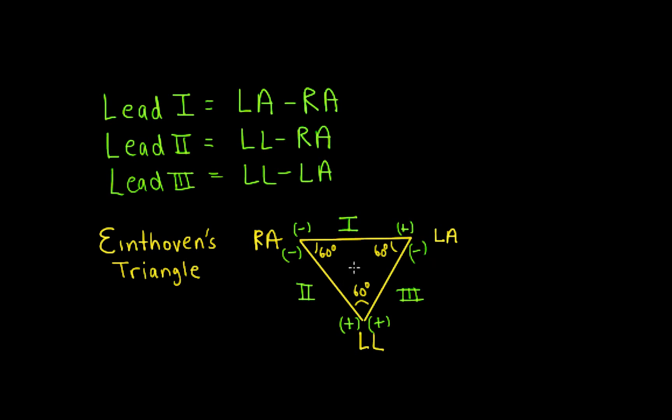If you look at the way the leads are organized, you can see that lead 1 plus lead 3 equals lead 2. The left arm electrodes cancel out when you add lead 1 and lead 3, and you're left with left leg minus right arm, which is lead 2. This relationship — lead 1 plus lead 3 equals lead 2 — is known as Einthoven's equation. It's good practice that when you're looking at an ECG, you quickly scan leads 1, 2, and 3 to see if this relationship holds. If it doesn't, the electrodes may not have been set up properly.